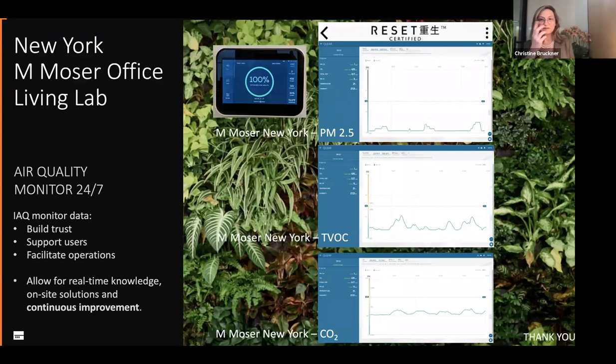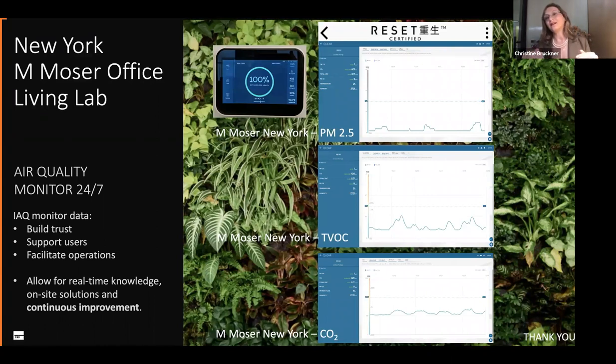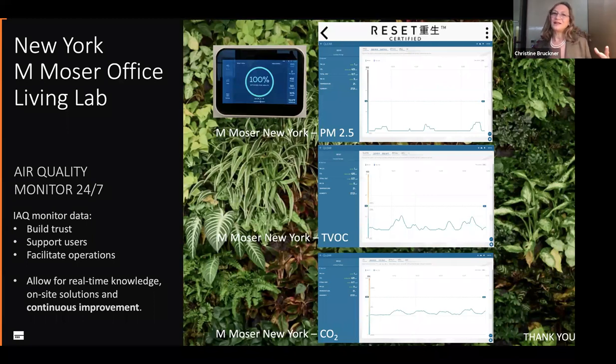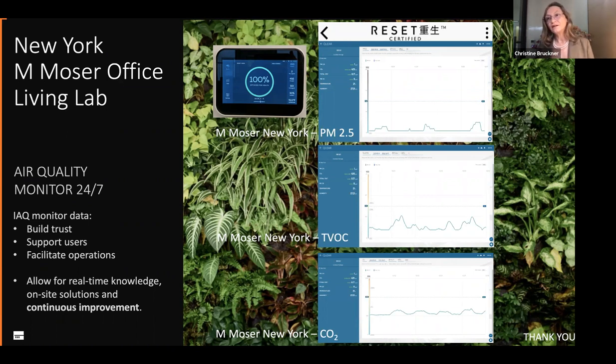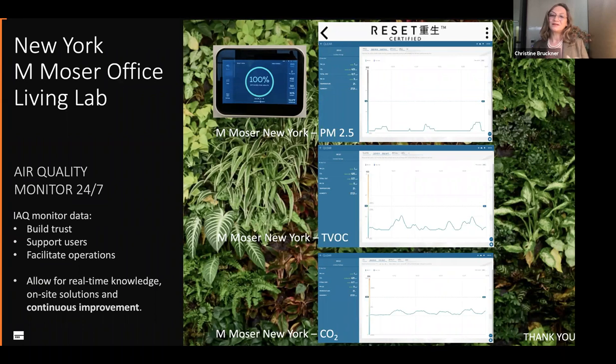Looking at the data screens: PM2.5 needs to stay under 15, and here we've got it immeasurable at around one to two — which is great. That means debris coming off chairs and tables is very minimal and we're recirculating and cleaning the air very well. TVOCs are down under the 500 mark, so total volatile organic components are minimal — no worries there. CO2 is a really interesting marker for how many people are in a space and how well your brain is working in a conference room. Keeping those levels low is very important, particularly with our current aerosol pandemic.